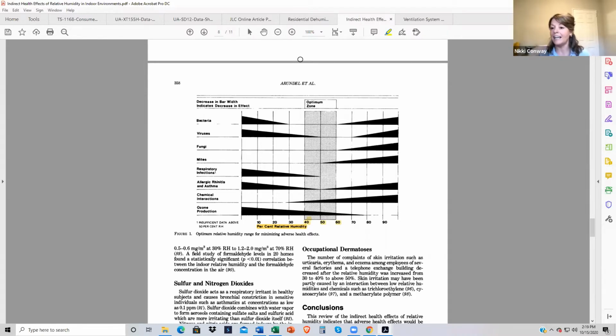And it's not just adding a dehumidifier. We need to look at those spaces and ask, do I have bulk water? Because a dehumidifier isn't going to fix that. Do I have a lot of infiltration from the outside coming into those spaces? Then we're going to have to do some air sealing and make sure we're setting up the dehumidifier to be successful and really control that space.